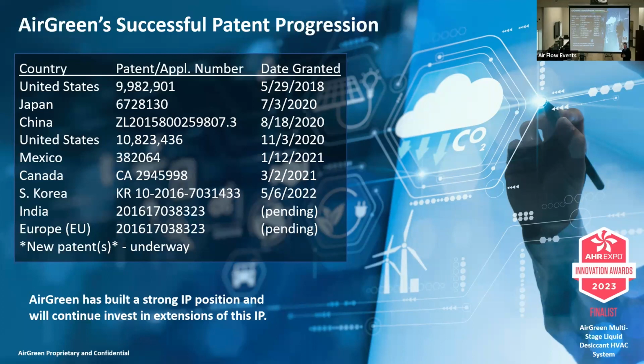And our technology, the patents are basically built around, we generally have our brine or desiccant flow counter to the airflow. We have a multi-stage system, and our desiccant feeds in on the last stage, and it circulates its way through as it reaches the first stage. That way, the driest air sees the strongest desiccant, so you can get a little bit more performance when you do it that way.